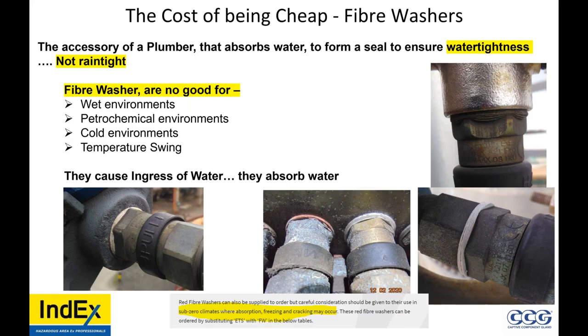Water is a serious issue for everybody's safety and for the longevity, the life, the maintenance of the facility. 6 threads of engagement only give you IP54. But there's other considerations. The surface roughness of the device. If it's a GRP, a plastic box, does the wall flex? Yes. Is it still IP54? No, not at all. So according to edition 7, you always have to have the sealing method to test for IP66.